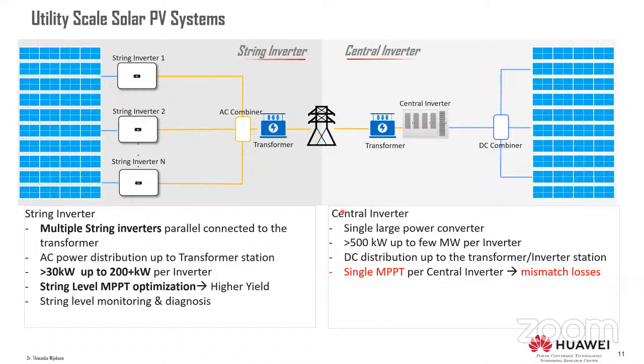So what is the difference and similarity between these two? Mainly, in a central inverter you rely on a single MPPT for the amount of power in the central inverter, which is typically in megawatts. So in case your plant has mismatches or partial shading scenarios, the whole generation will be dropped, since you're optimizing for the whole plant.